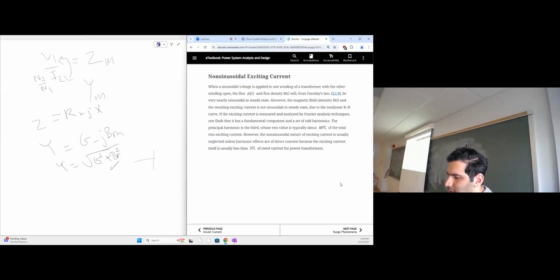Non-sinusoidal exciting current. As you have seen before, we are applying a regular sinusoidal voltage on the primary end. However, because of the nonlinear characteristic of the transformer, the generated currents will be of non-sinusoidal structure. And that could cause problems to different machinery and to different circulations of current. So this is something to consider, that exciting current, which counts for maybe 5% of the loss in the transformer, could cause problems. So our goal is to make sure that value does not exceed that limit, to do all the necessary testing and all the necessary tuning, to make sure that value won't exceed 5%. So who could remind us what the exciting current is? I think it's made up of coupled currents added up together. Who can remind us of that?